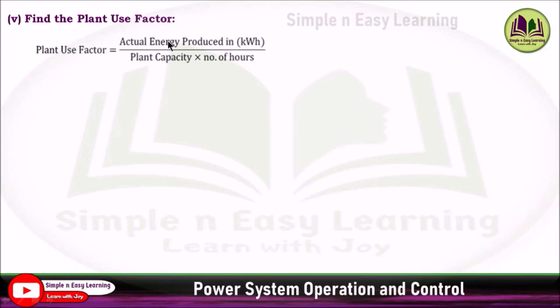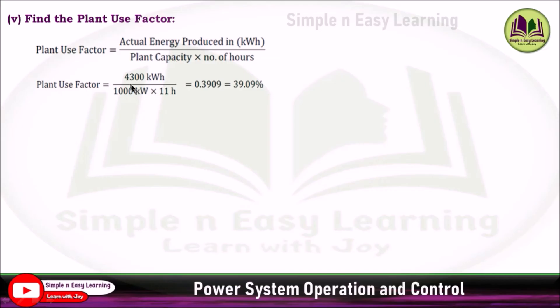Find the plant use factor. Plant use factor equals actual energy produced in kilowatt-hours divided by plant capacity multiplied by number of hours in use. Actual energy produced is 4300 kilowatt-hours divided by 1000 kilowatt capacity, and the number of hours the plant is used is 11 hours. Out of 24 hours, only during 11 hours is load consumed. The plant use factor is 0.3909, or 39.09%.